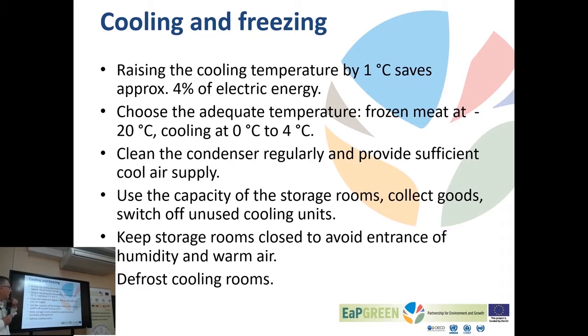Small thing, but can add up. So let's choose the adequate temperature. Let's not go for the least temperature possible, but for the adequate temperature. A clean condenser allows a good heat transfer, reduces the temperature of condensation, and has a very similar effect to increasing the temperature of cold, because it will reduce the temperature of condensation. So cleaning the condenser frequently or regularly will reduce electricity requirement.